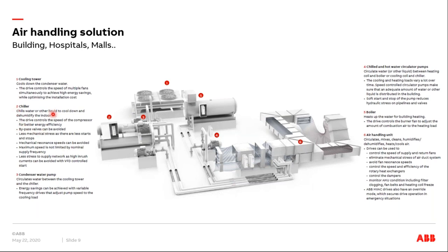So you have the chillers, which are basically compressors. Then you have the water condensing pumps. And number four, what you see here is the circulating pumps, because you need to circulate the hot and cold water within the building. You have the boilers that require fans. Also, the drives are used to adjust the burner fans for the boilers. And then you have the air handling units, which are basically humidifying, dehumidifying, mixing air, and cleaning, to make sure that the air is clean. These are mostly fans. So it's a lot of fans, pumps, and compressors here.